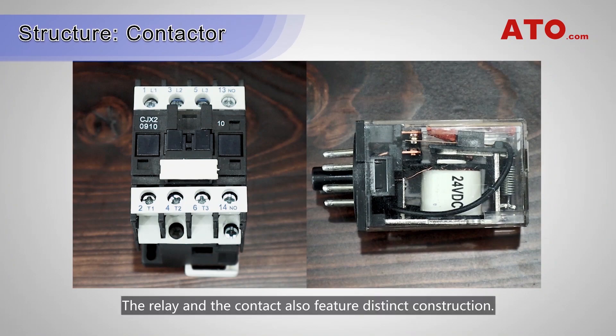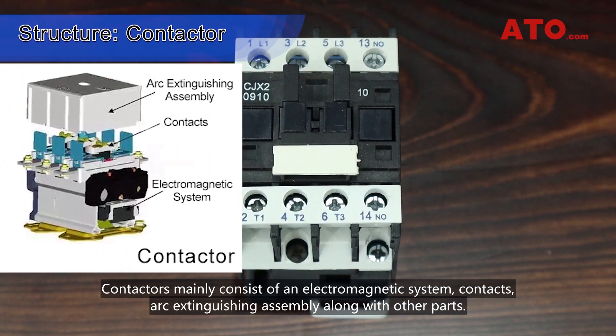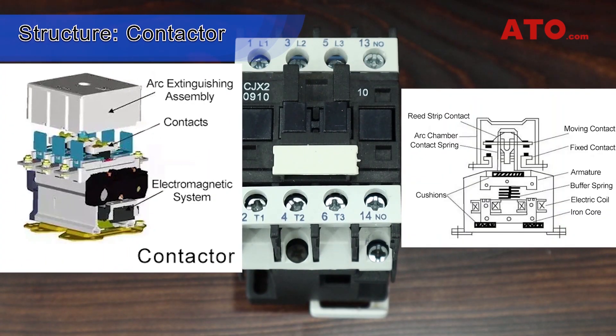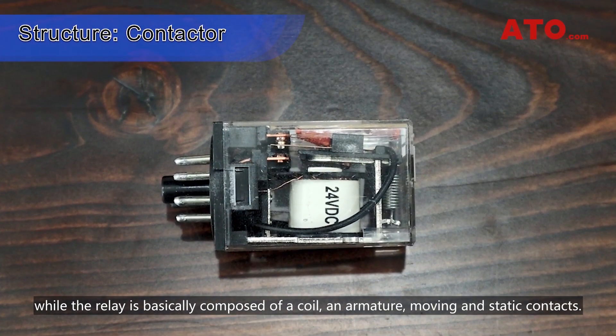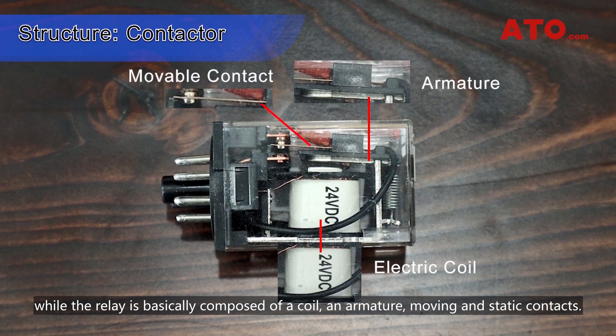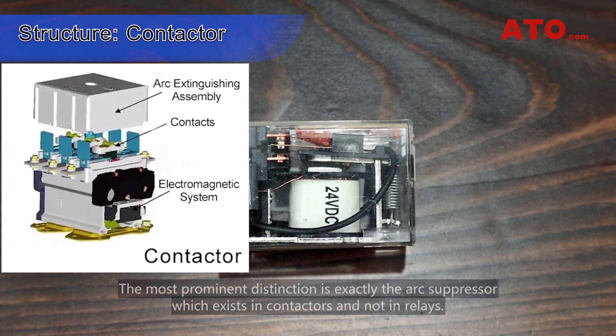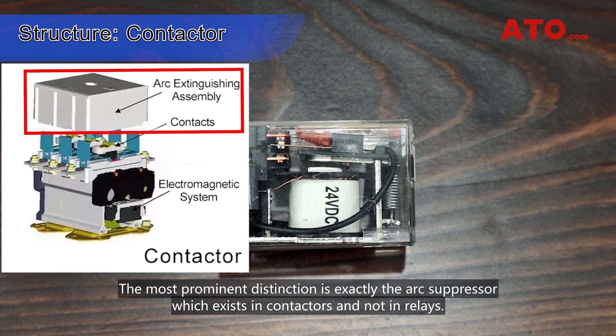The relay and the contactor also feature distinct construction. Contactors mainly consist of an electromagnetic system, contacts, and an arc extinguishing assembly along with other parts, while the relay is basically composed of a coil and armature, and moving and static contacts. The most prominent distinction is the arc suppressor, which exists in contactors but not in relays.